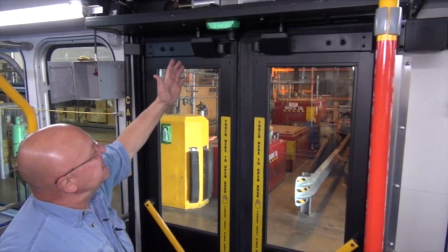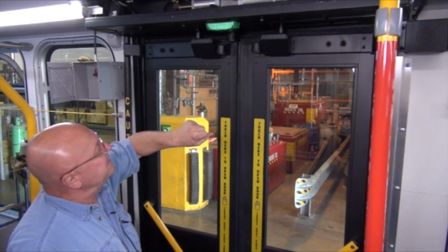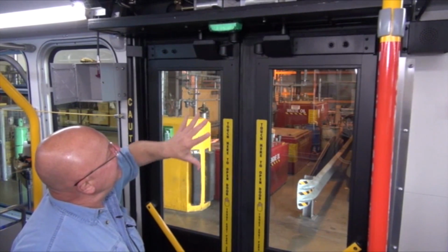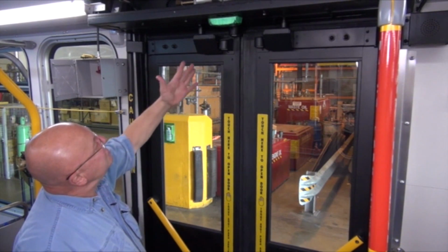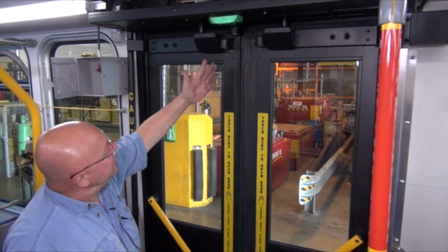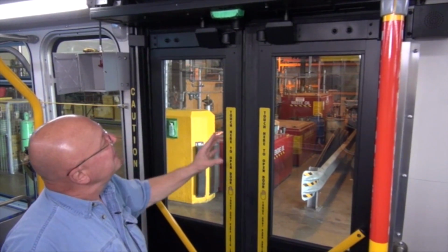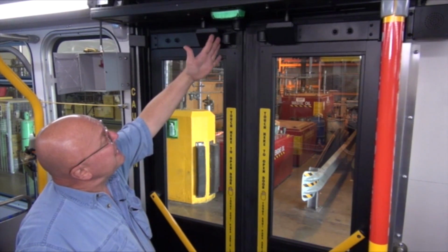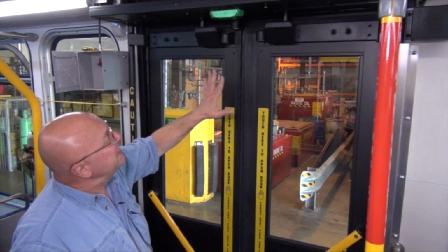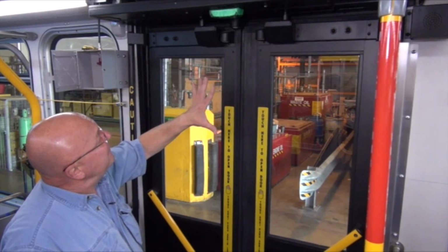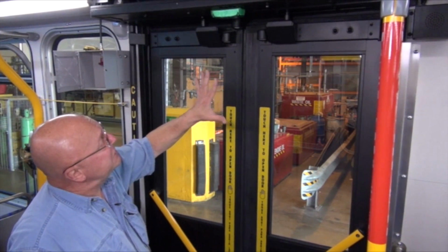Basically what happens is when the driver enables the exit door, these three sensors become active, and initially they control the passenger request to open. They also provide an enhancement for the door edge safety to prevent the door edges coming into contact with passengers, and also the middle sensor is active and keeps the doors open as we have a stream of passengers exiting the door, and in fact stops the door going into a flapping mode and reduces the dwell time as a result of that.